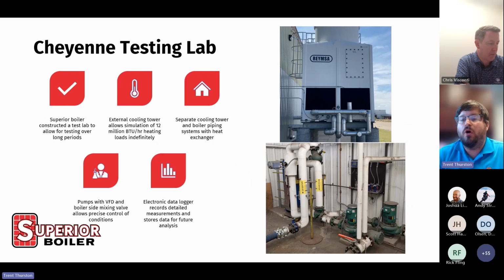So this is our newest product, but we have tested it thoroughly. In about 2020, we built our test lab and have tested these boilers since then. In our test lab, we have a cooling tower, which allows us to operate for extended periods of time. Another factor is we have a heat exchanger, because the boiler loop is a closed loop and requires different chemical treatment than the cooling tower loop, which is open and requires treatment for algae, among other things.